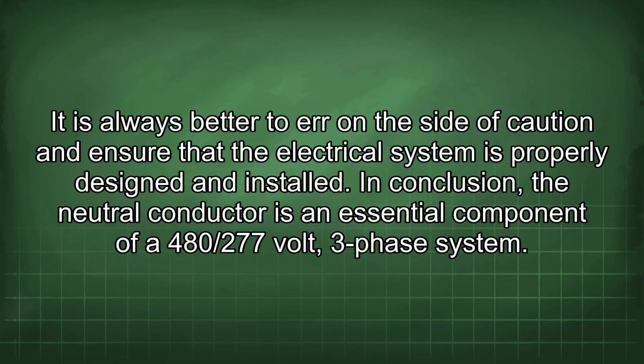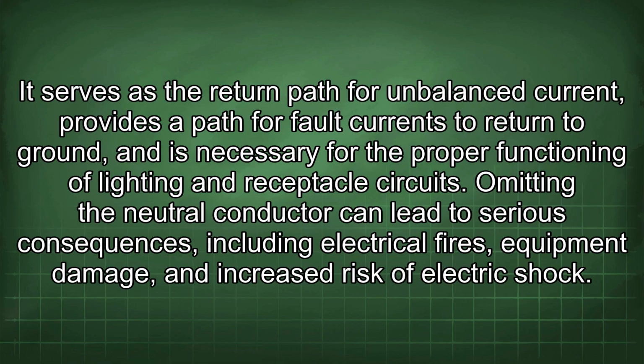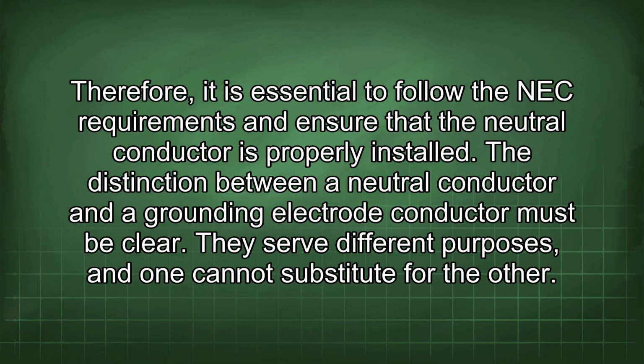In conclusion, the neutral conductor is an essential component of a 480/277 volt three-phase system. It serves as the return path for unbalanced current, provides a path for fault currents to return to ground, and is necessary for the proper functioning of lighting and receptacle circuits. Omitting the neutral conductor can lead to serious consequences, including electrical fires, equipment damage, and increased risk of electric shock. Therefore, it is essential to follow the NEC requirements and ensure that the neutral conductor is properly installed.